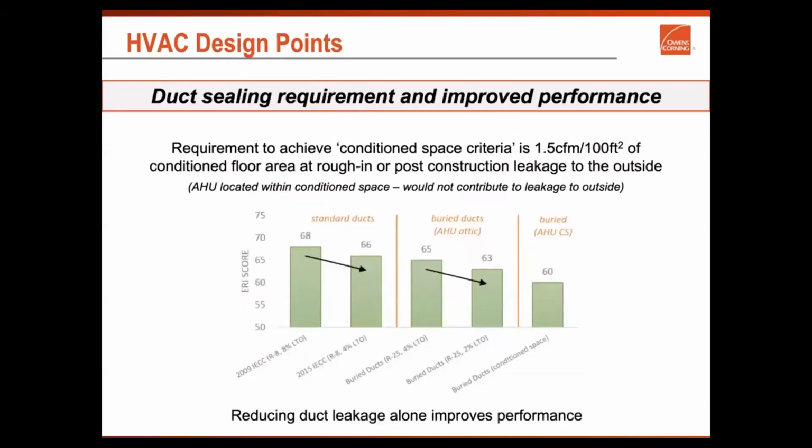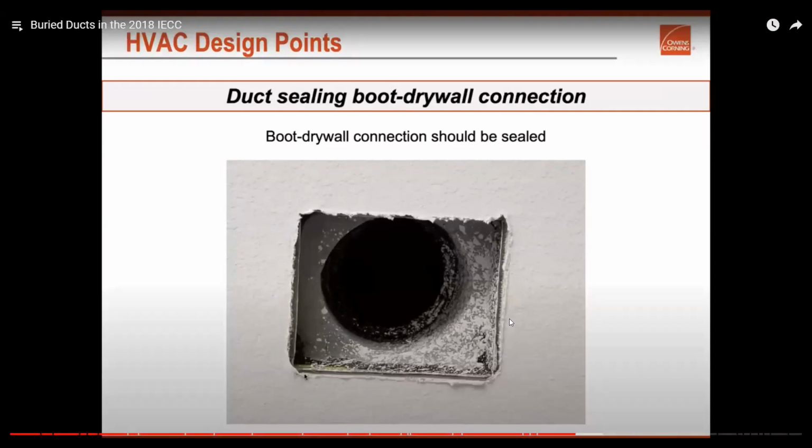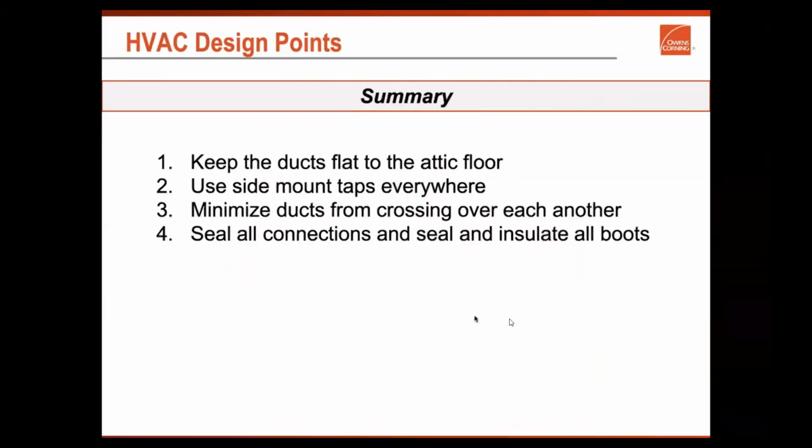We talked about this already, right? Boot connections should be sealed, as always. And one thing I always tell builders is, when you give the painters the option to caulk the register, what they do is they caulk it to the ceiling. But what they were paying for was caulking this little joint here. That joint is crucial to making sure that we keep our airtight layer.